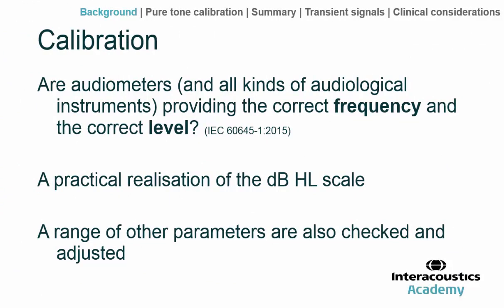Fundamentally, when we want to ensure the pure tone audiometer is performing correctly, we need to answer two questions: are the pure tones being emitted at the correct level and at the correct frequency? Over time, changes in level or frequency — sometimes described as drift — can occur. Also, mechanical or electrical failure or mishandling can affect frequency and level, amongst other things.